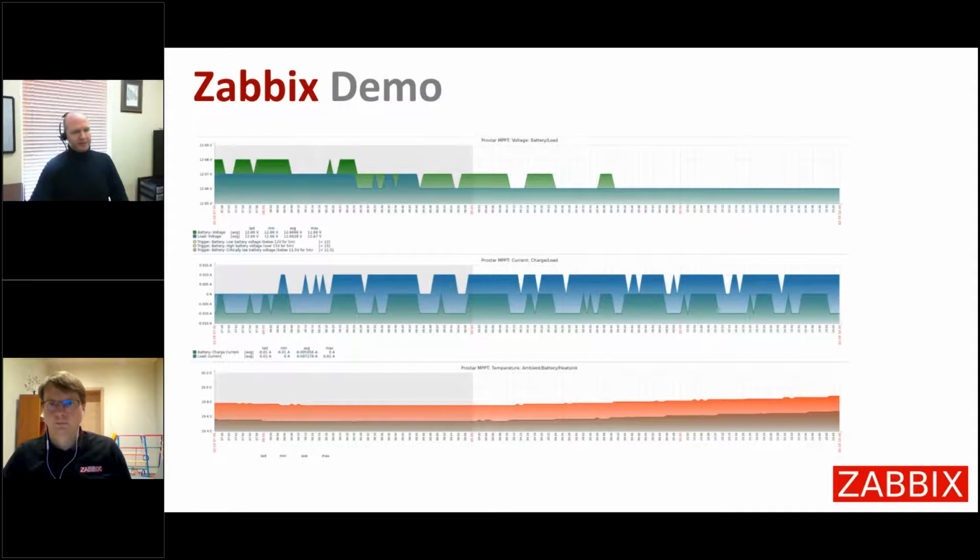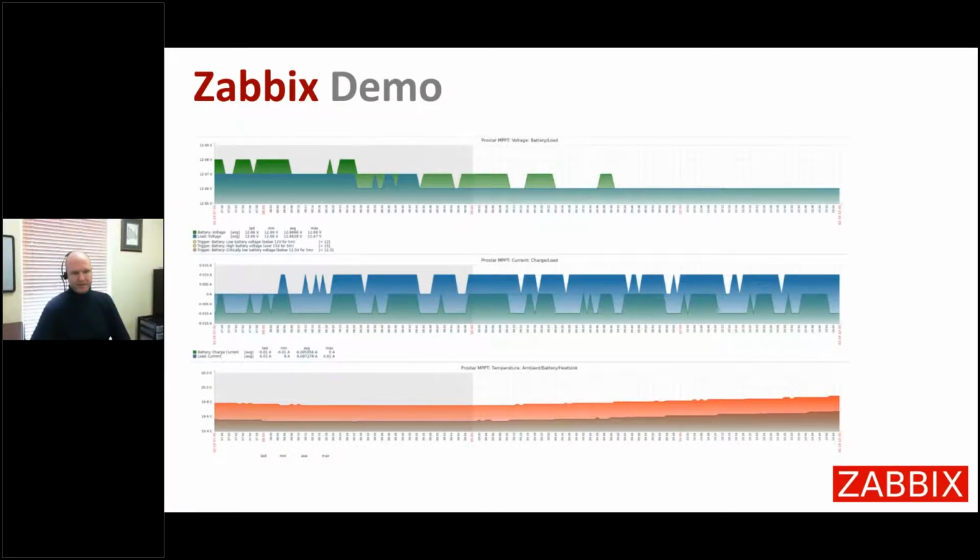One of the things I could speak to here, because we've got the graph up as we transition to the next section, is that when you get the granularity of data that's enabled by this system across all these devices, there's a considerable amount of insight that you can gain from that. It takes understanding off-grid systems and what the expected behavior is, and then the ability to capture all of that through remote communications. So for instance, if you look at these graphs over a week, a month, a year, or many years, you can see a battery age over many years and when it's getting ready for replacement.